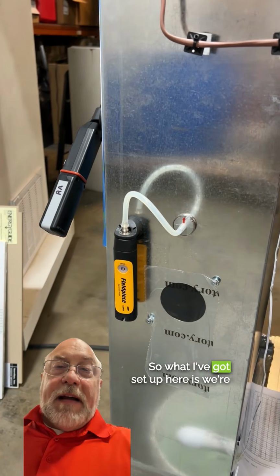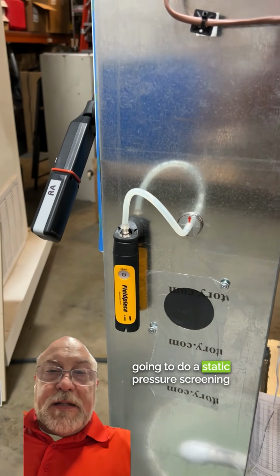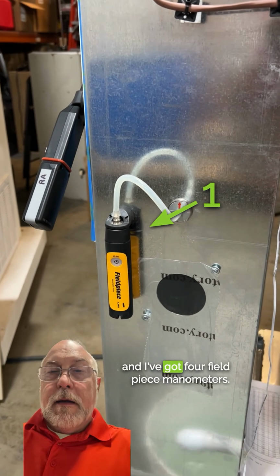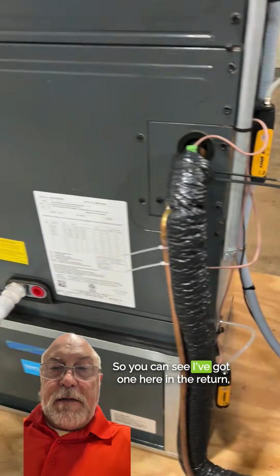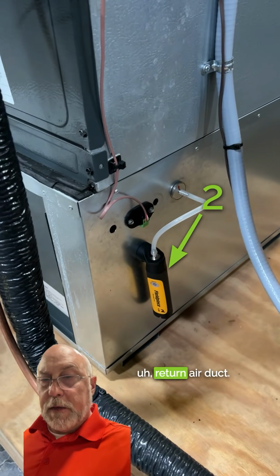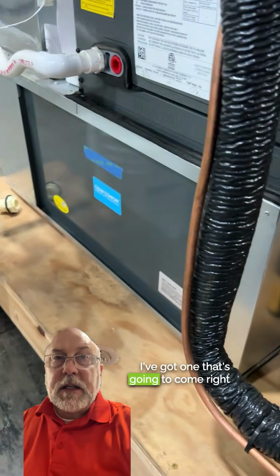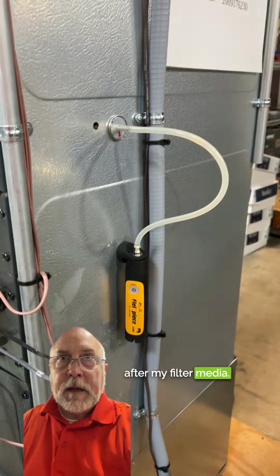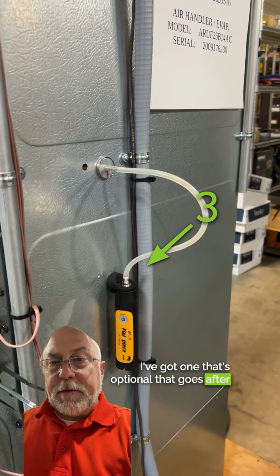So what I've got set up here is we're going to do a static pressure screening, and I've got 4 Fieldpiece manometers. So you can see I've got one here in the return air duct. I've got one that's going to come right after my filter media. I've got one that's optional that goes after the evaporator coil.